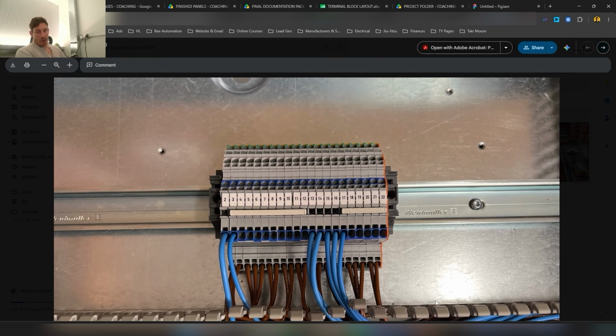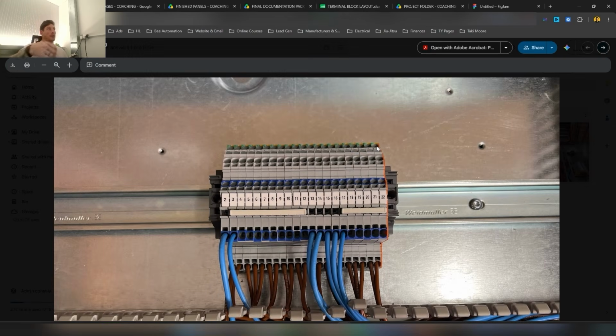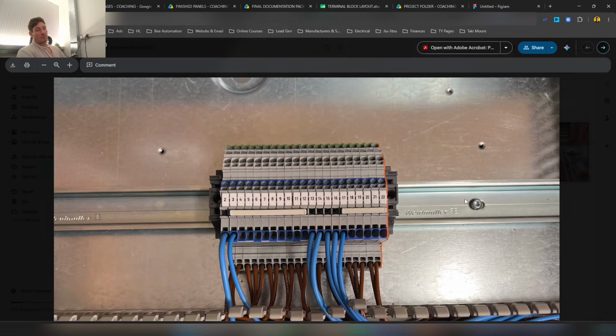But you can see that we haven't got an inbound earth cable on this side. The earth, as you can see, the outbound earth that's going to be going to lighting circuits, HVAC control circuits, boiler on/off, domestic hot water on/off, controlling valves open and closed, is picking up the earth here from this DIN rail. There's metal hooks within these terminal blocks picking up the earth from the DIN rail. So we just want to make sure we've got a solid earth connection feeding the enclosure, if you like.